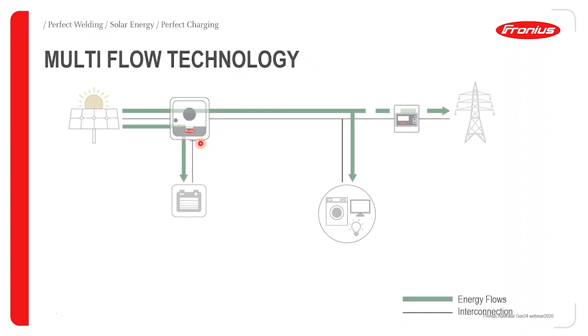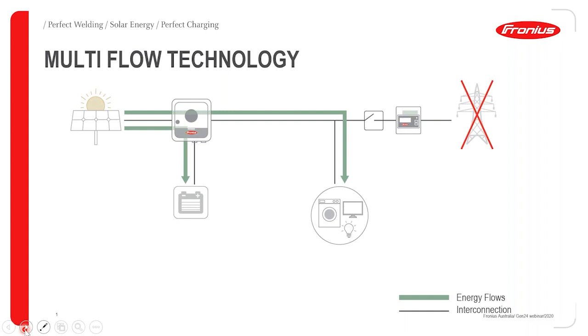For example, if you have a Symo GEN24 with a smart meter and a battery, you can charge directly from the PV to the battery, and also send power from the PV to your loads or to the grid at the same time. So with a Symo 10, you could get 10 kilowatt directly from the panel to the loads and charge 5 kilowatt directly to the battery simultaneously. This is one of the features of the multi-flow technology.